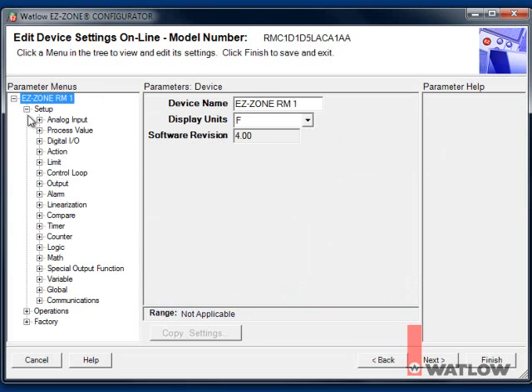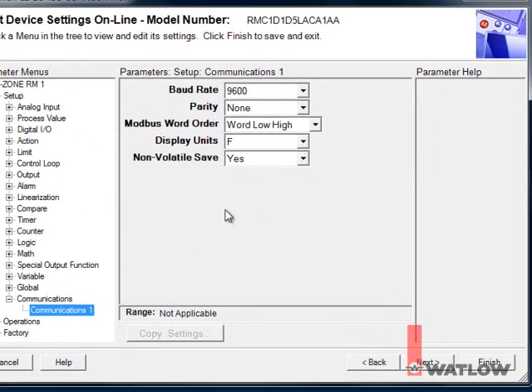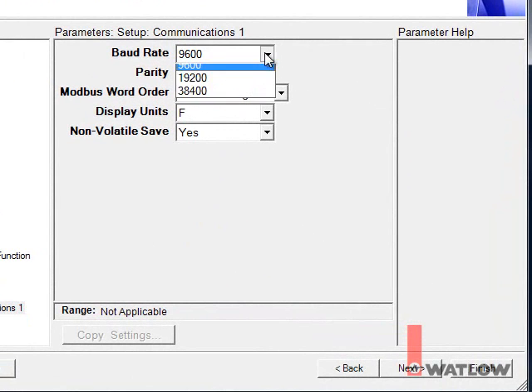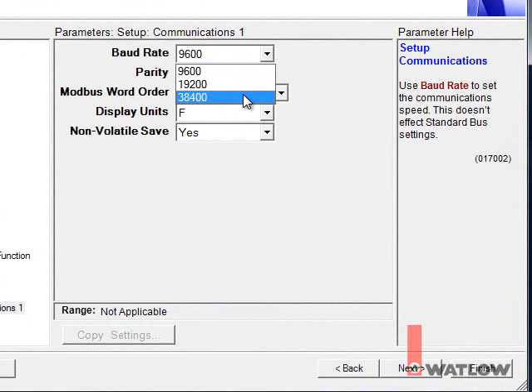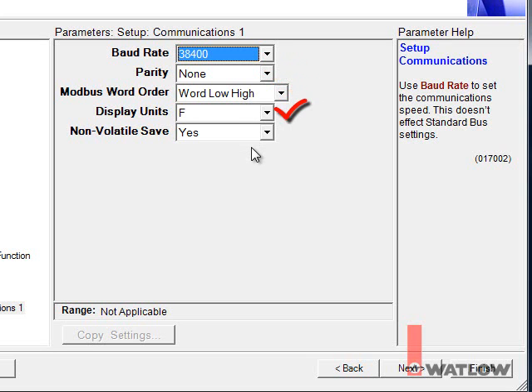...and set the baud rate. We'll use 38,400. Set the parity to None. Set Modbus Word Order to Word Low High. Set Display Units to the temperature scale you want. And set Non-Volatile Save to Yes so that the parameter values you change via the OIT will be retained in the controller's non-volatile memory.